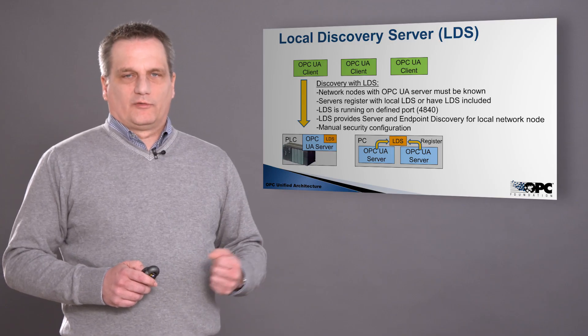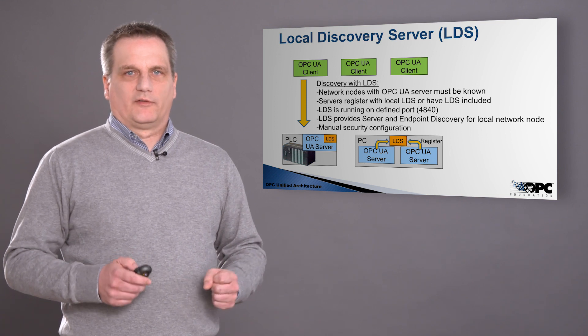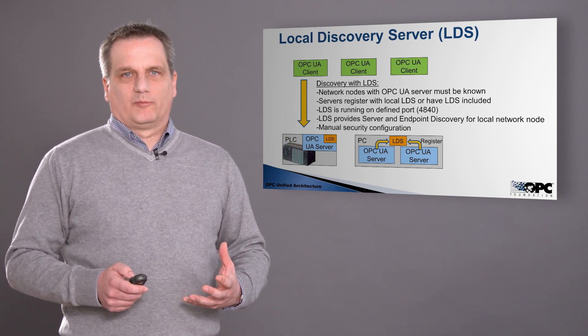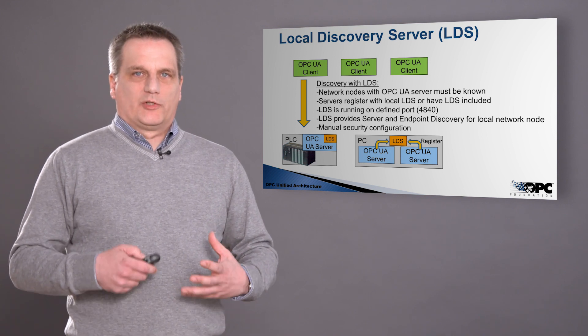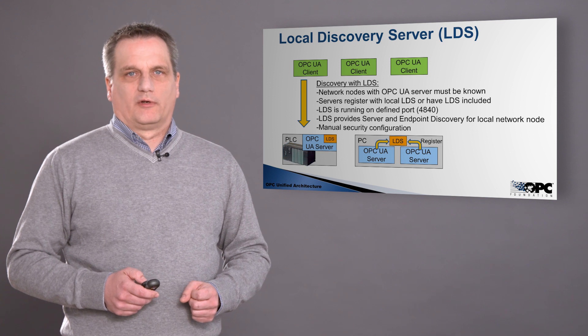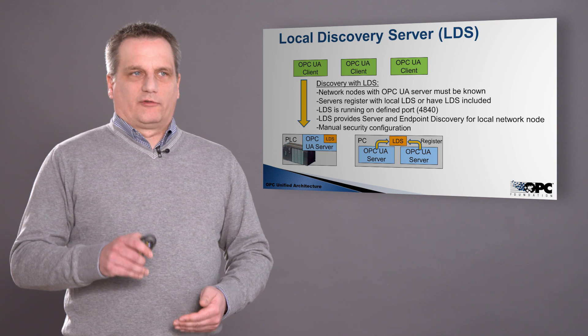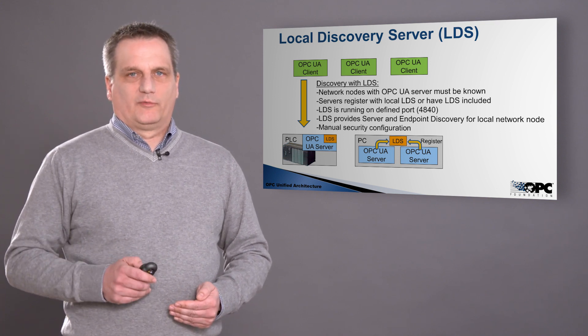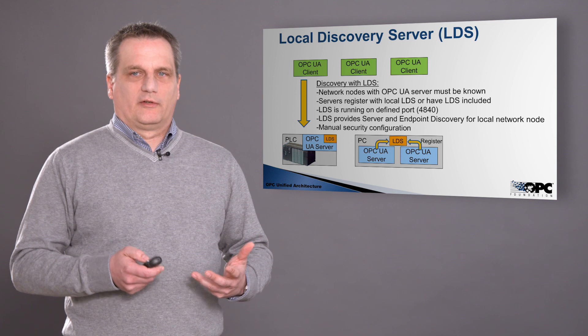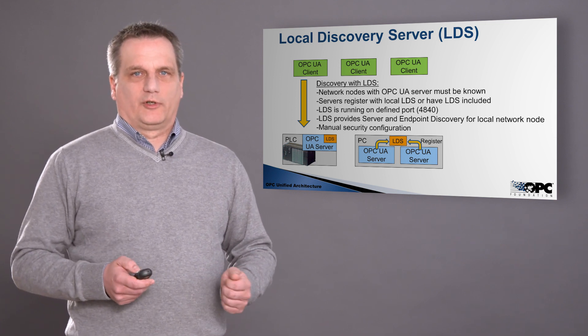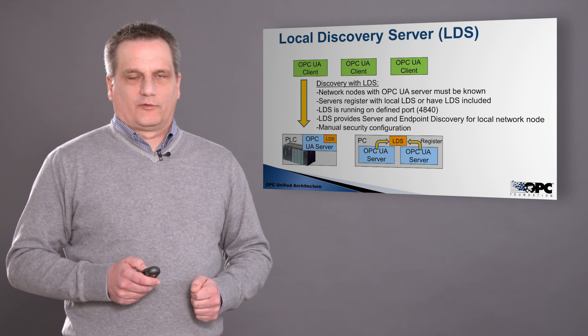If there's only one — like for example in a PLC you typically have only one OPC server running — then this server will present itself. But on a PC-based system where you have multiple software installed, which can all have their own OPC server, there will be a local discovery registration where all the servers register themselves, and then the client can always access port 4840 and either finds only the one server on that machine or finds a list of servers on that box.